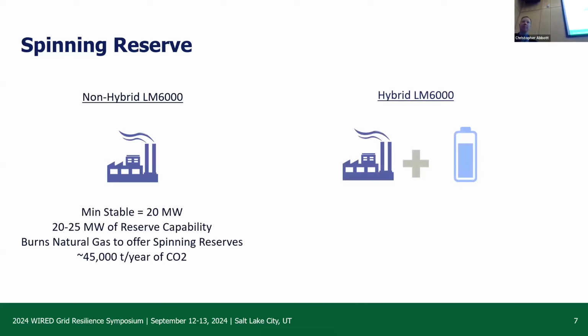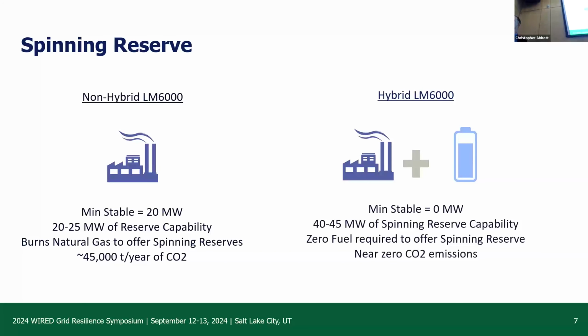The battery in the hybrid allows the asset to be connected to the grid with the gas turbine off. Battery can react in real time, putting power on the grid in a moment's notice and long enough that we can start the gas turbine to provide more energy than the battery is capable of if we get called on by the grid operator. Here's what that looks like. That takes the minimum stable generation down to 0 megawatts. Now we have the full capacity of the gas turbine that we can sell as spinning reserve. Because we're at 0 megawatts and the gas turbine's offline, there's no emissions.